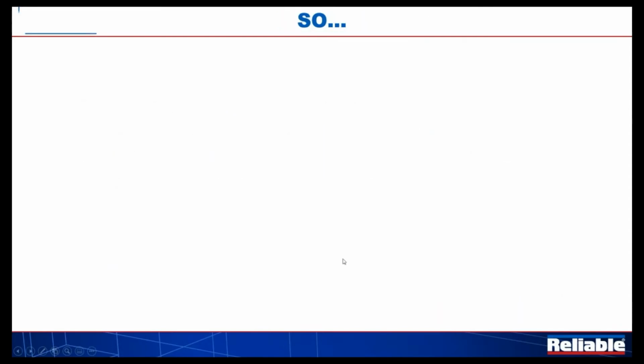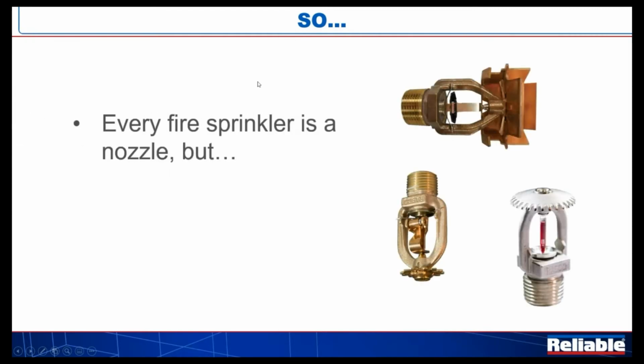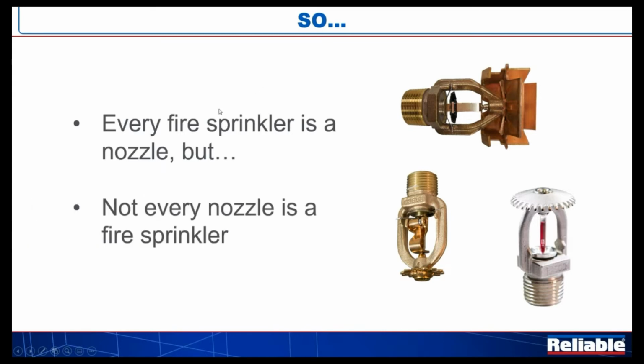So there's your definition. So in that regard, by the definition, every fire sprinkler is a nozzle. It does exactly what the definition says. And there are some obviously fire sprinklers on the screen, but not every nozzle is a fire sprinkler. And I tried to find out what type of argument that is, and it leads down a massive rabbit hole of logic and philosophy and all that. So don't go there. But every fire sprinkler is a nozzle. Not every nozzle is a fire sprinkler. Nozzles are tested and listed to a different standard, either UL 2351 or FM 2025. Whereas we should all know by now, for fire sprinklers, the basic for UL is 199, and for Factory Mutual is FM 2000. So they have their own testing criteria.